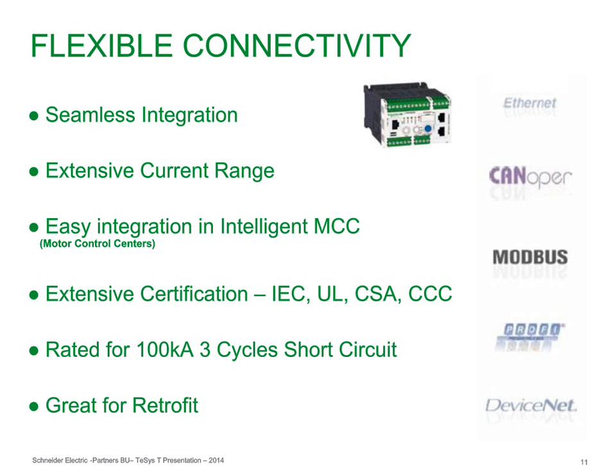So it has quite a good capability there. And again, it is designed for retrofit of existing units, so we can actually turn older motor control centers into smart motor control centers by integrating TeSys T into the design. Now, setting this up is only as good as the software, and we actually have a software called SoMove. It's very intuitive. It's PC-based software so that you can actually program multiple units here, either via the network or there's a front connection you can put in right from a PC.